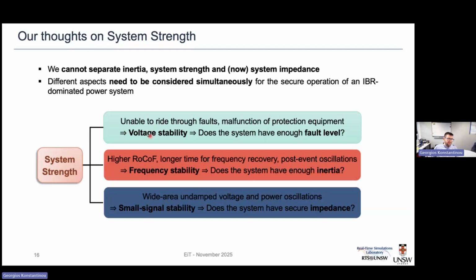In the end, we need to understand that we cannot really separate the different elements. We cannot separate inertia, system strength, and system impedance, looking back at that equivalent network. All of them need to be considered simultaneously to ensure safe and secure operation of the network. So whatever we use to define a strong or weak grid needs to capture fault level, inertia, and elements of impedance at a particular point in the network and whatever connects to it, to ensure a stable system following faults, frequency events, and to avoid oscillations and interactions between different elements of the system.